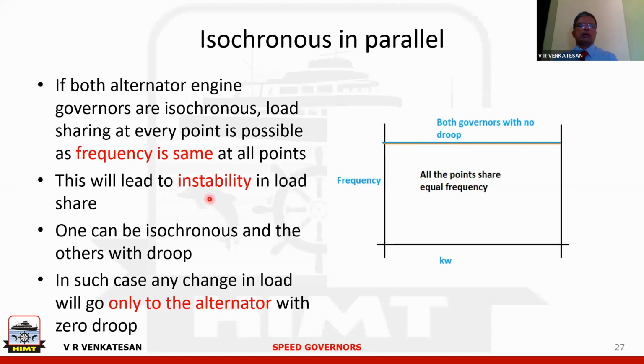So if you don't want instability, the point is simple: there must be a single intersecting point, which will say this is the busbar frequency. So how to achieve this? You can run both with droop, which is the most common arrangement, or you can have one isochronous and the other with droop. If I have one isochronous, it will be a horizontal line, the other is at an angle, and you will still get a single intersecting point. If you have one isochronous and the other with droop, then the change in load will only go to the alternator with zero droop.